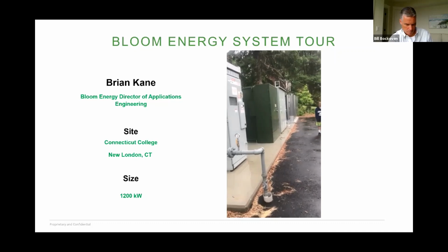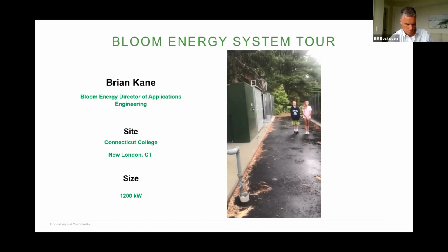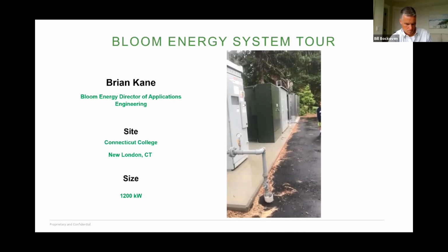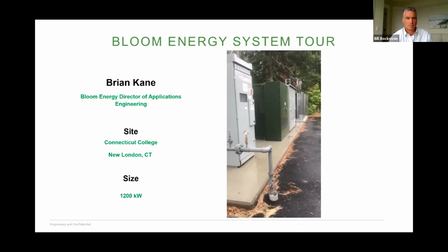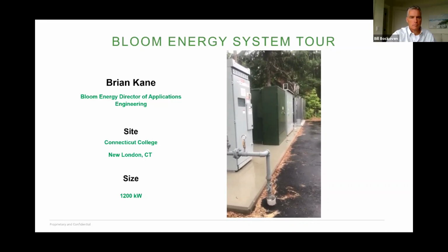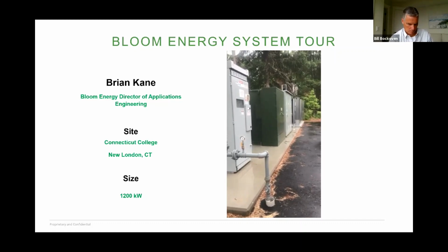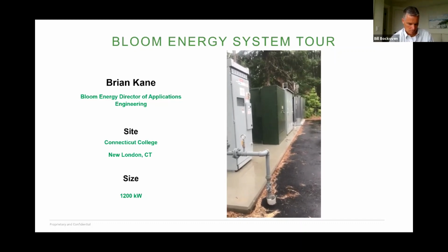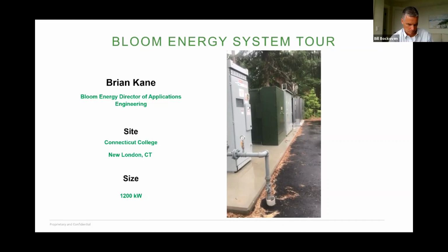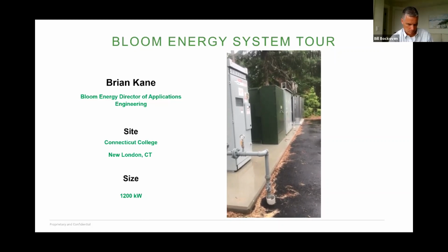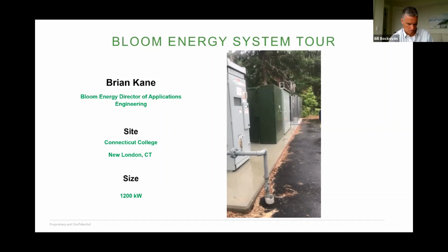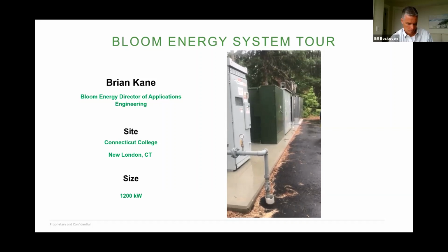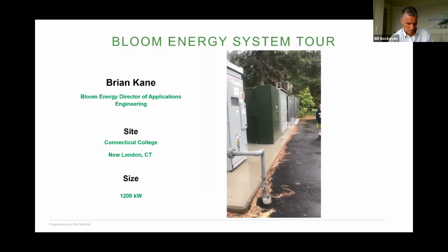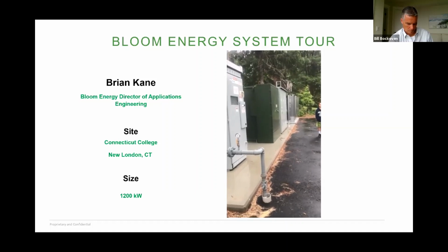Where Max and Anya are standing, to Maximilian's right, is a 480 volt switchgear cabinet that aggregates the 5 energy servers on site into a common 480 volt AC bus and then connects to the green transformer, which transforms it to 13 kV here at the Conn College campus, distributing power directly to all of the consumption on campus.